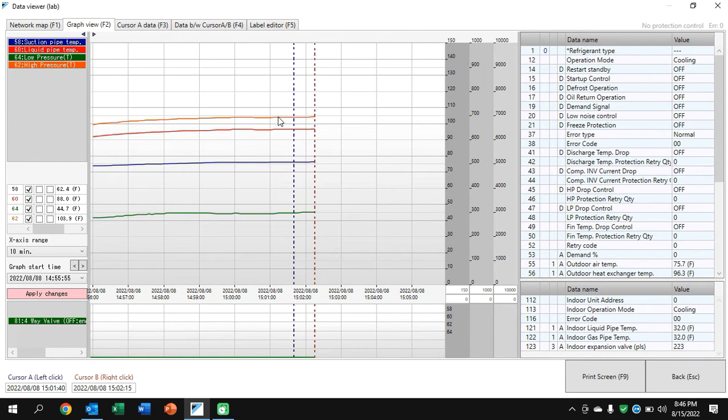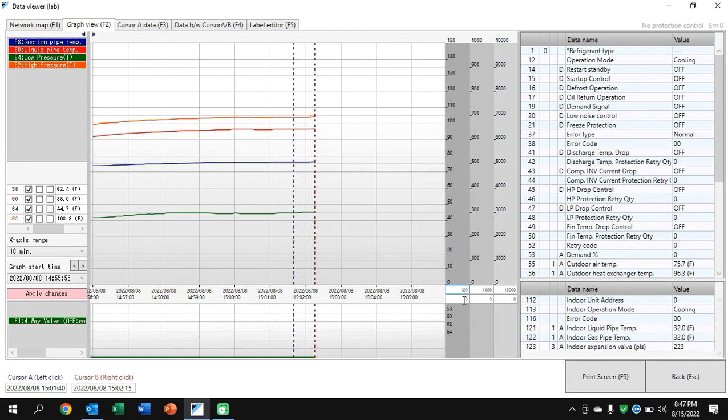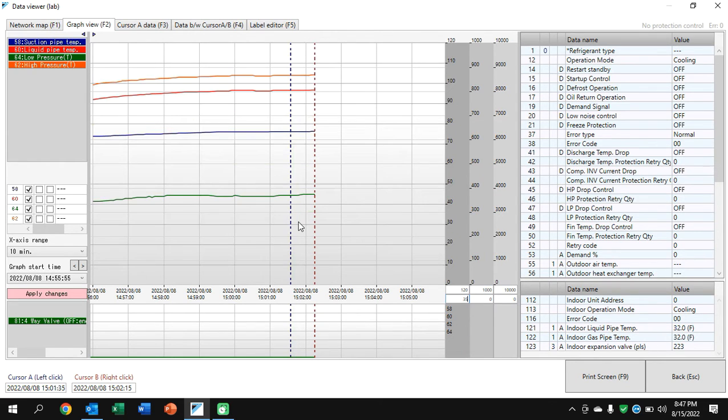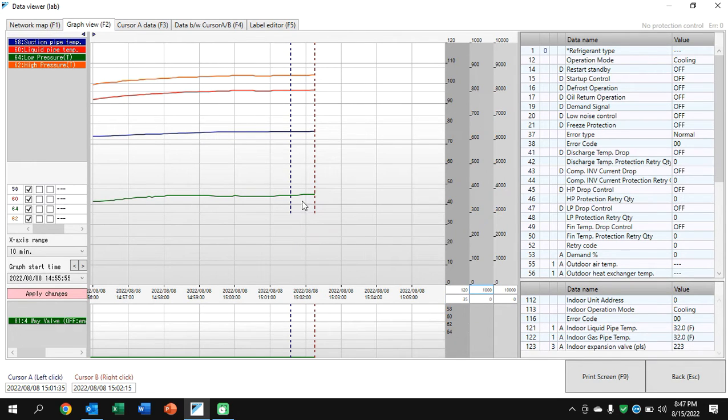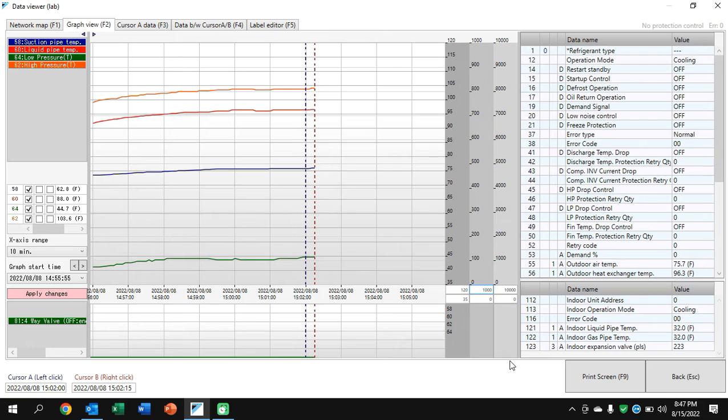So now I can see on the chart here. Now, the chart's not super linear. So when we look at the numbers on the left, we'll see maybe 18 and 18. But you'll see it looks a little wider on the way the chart's laid out. But as long as you know that, we can enter numbers and just get the proper data just on the screen that we want to monitor while it's running. And we can look for a difference. And if we see the lines getting too close or too far apart, any point you feel it's alarming, we can look over to the left there and get the actual data. And you'll see as I move along the timeline, we'll update the data. And when you're doing it live, it'll update every five seconds.